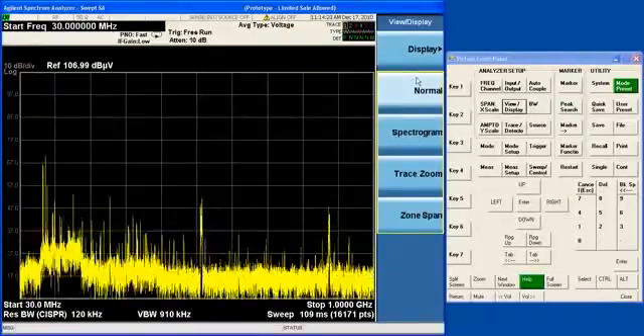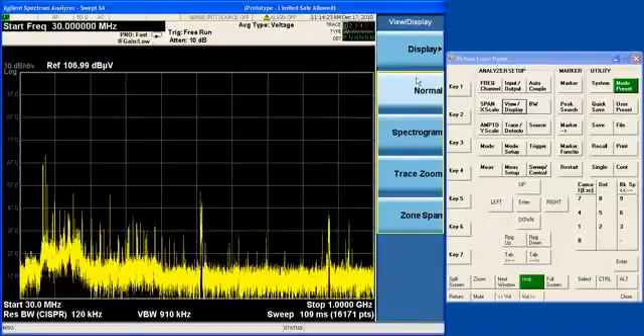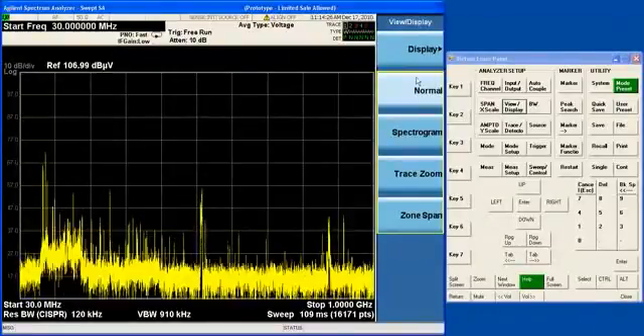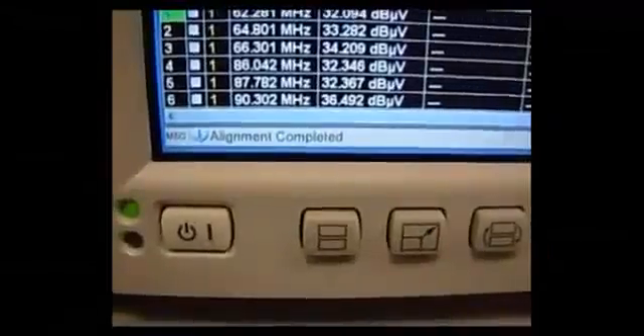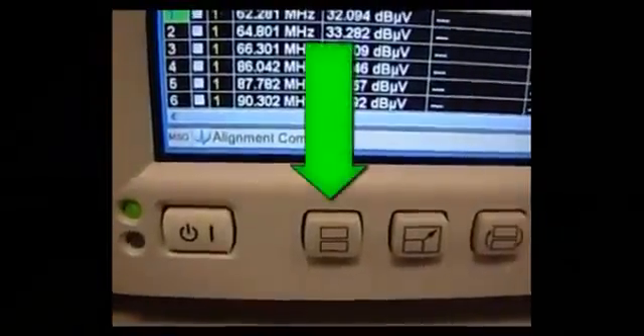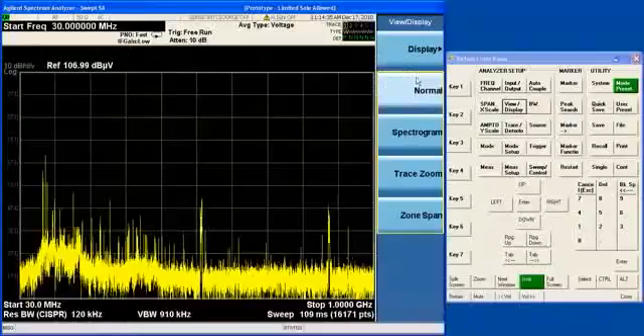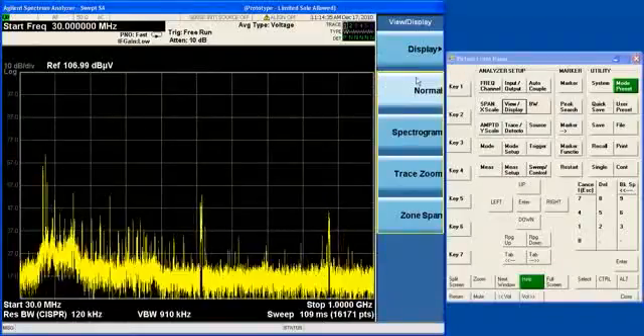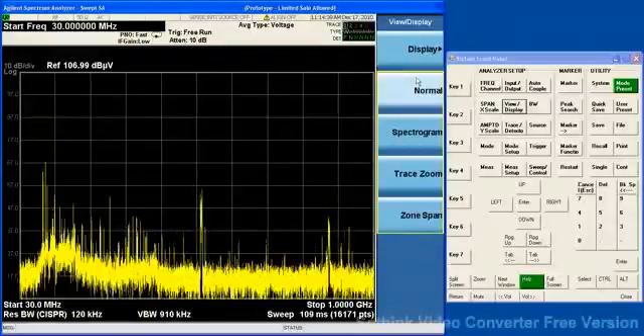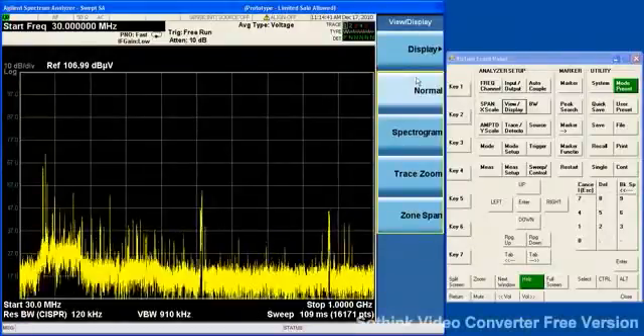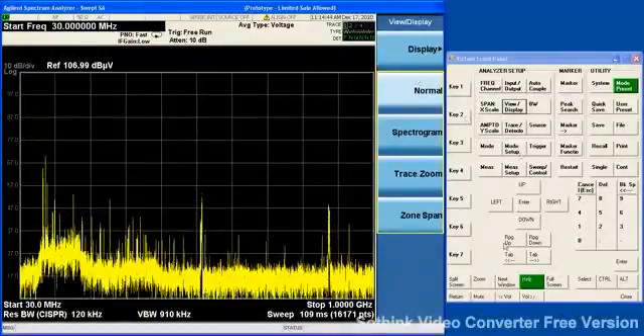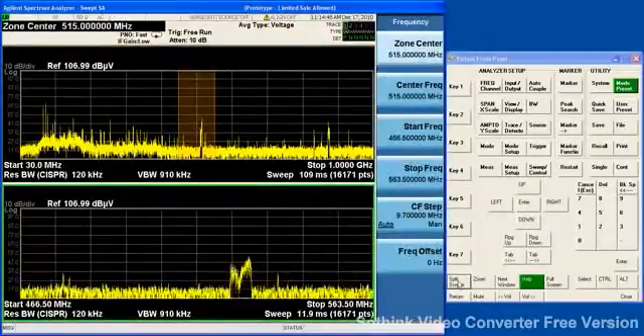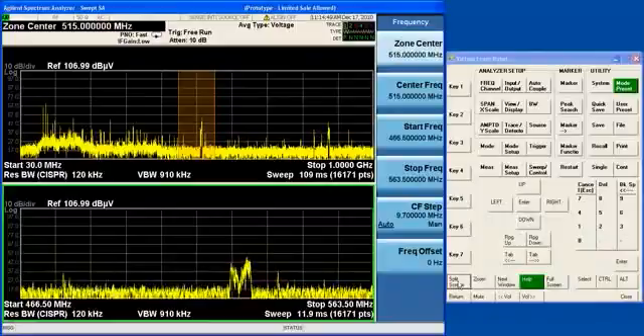Now, the easiest way to get into one of these views is to simply press the Split Window hard key on the front panel. This key appears below the display. It looks like two rectangles, one on top of the other. If you press this key, then it will put you into the Zone Span view by default. So let's push the Split Screen key, and that puts you into the Zone Span view.